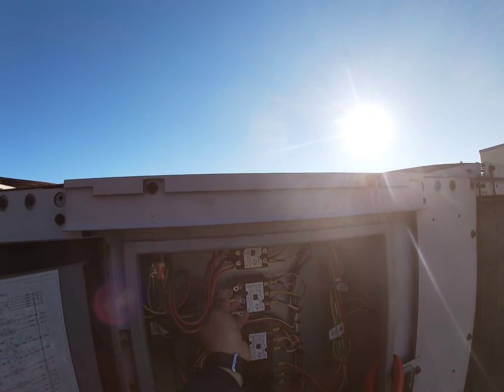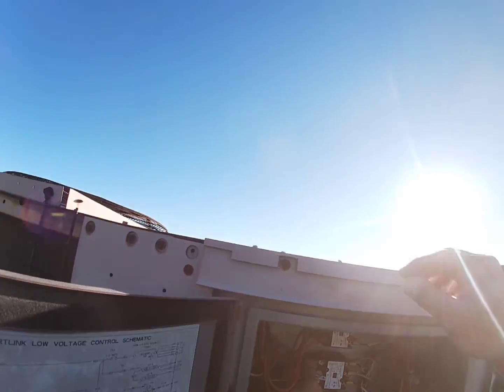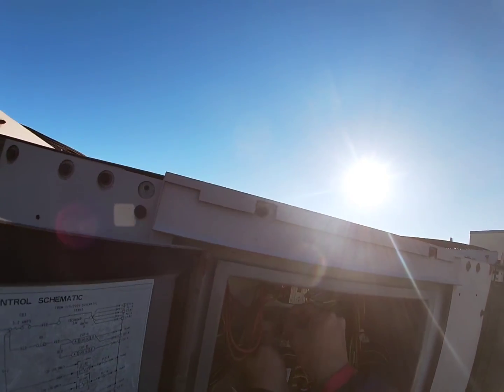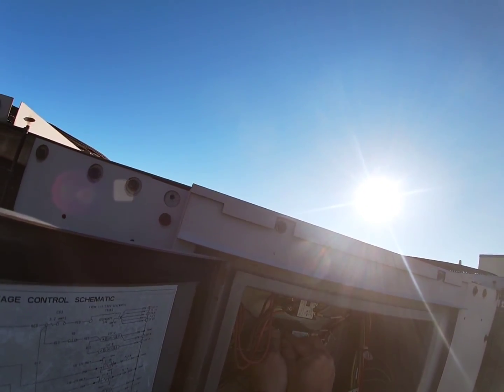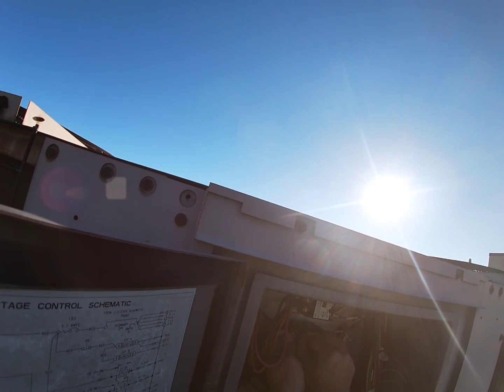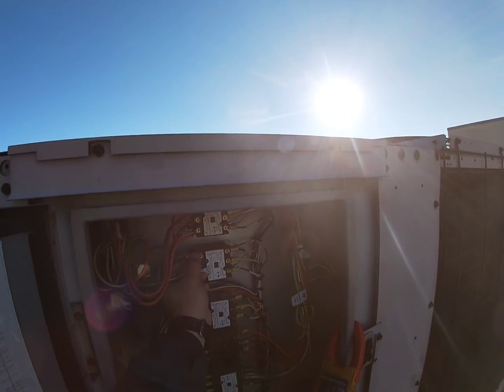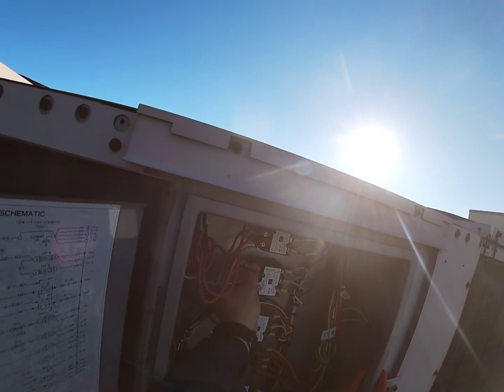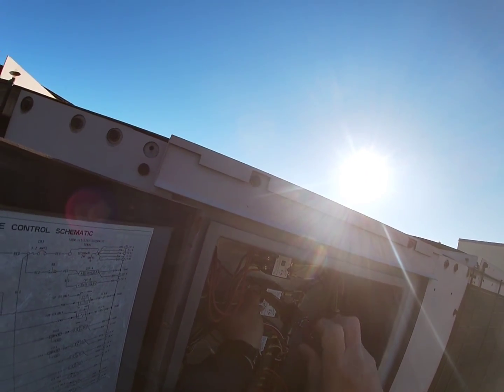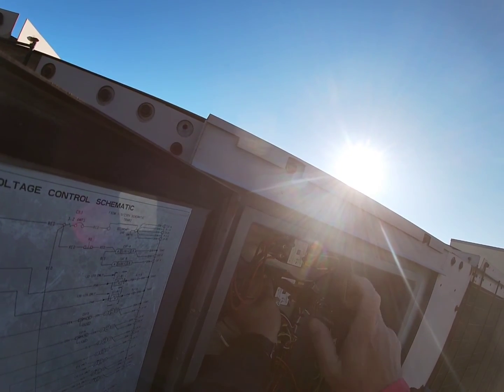7.1. So sometimes it might get a little weird, especially when you're ohming out a condenser fan motor, and your condenser fan motor might be moving in the wind. You will get some weird resistance values as well, but I feel we're okay with this motor. I think it's just that one motor there that caused us an issue.